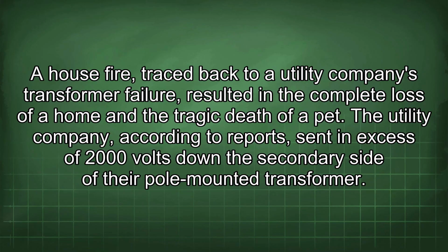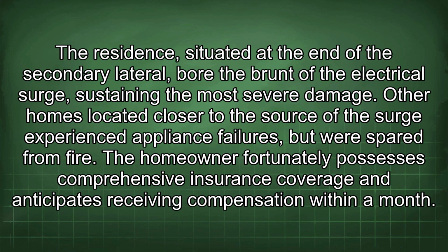A house fire, traced back to a utility company's transformer failure, resulted in the complete loss of a home and the tragic death of a pet. The utility company, according to reports, sent in excess of 2,000 volts down the secondary side of their pole-mounted transformer. The residence, situated at the end of the secondary lateral, bore the brunt of the electrical surge, sustaining the most severe damage. Other homes located closer to the source of the surge experienced appliance failures, but were spared from fire.